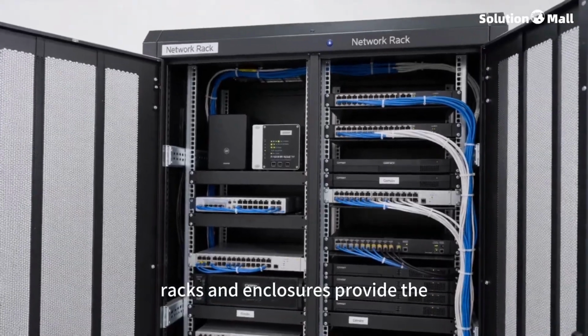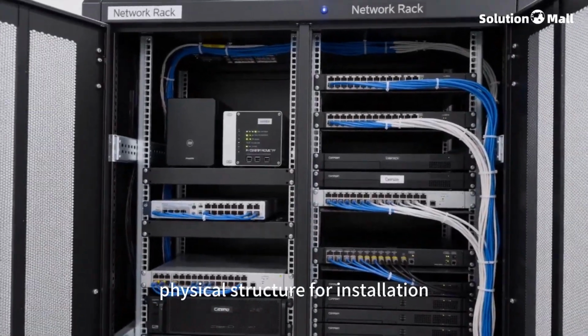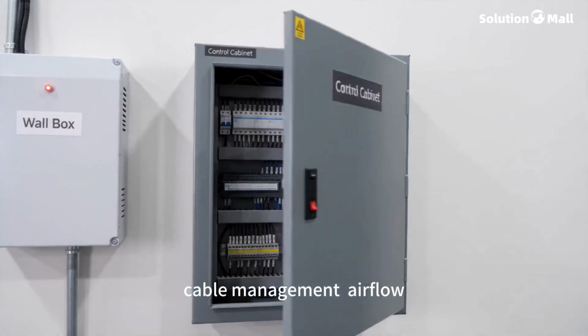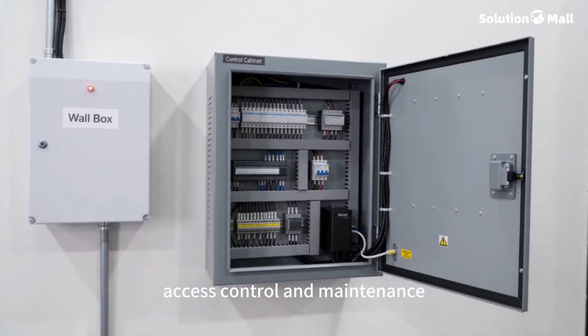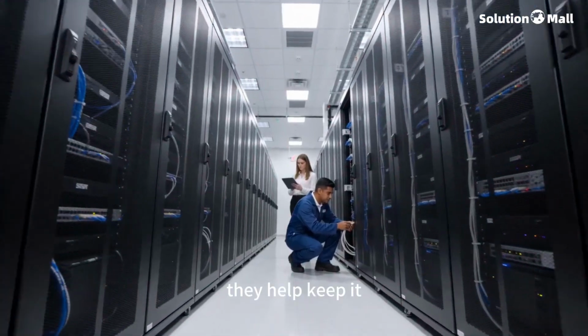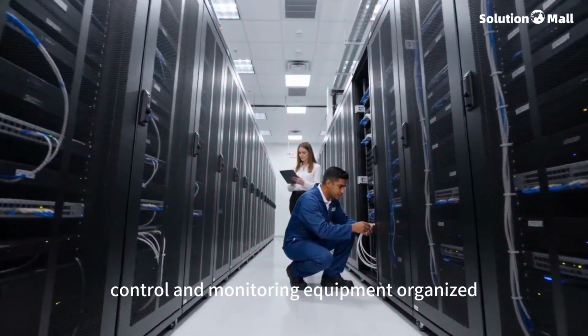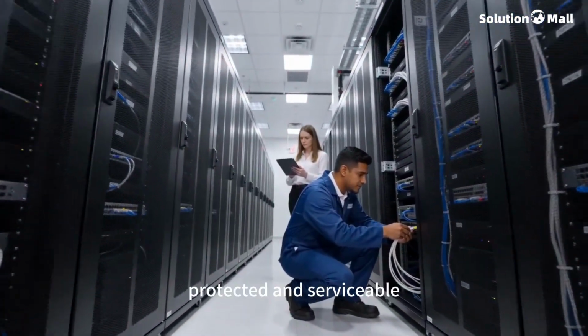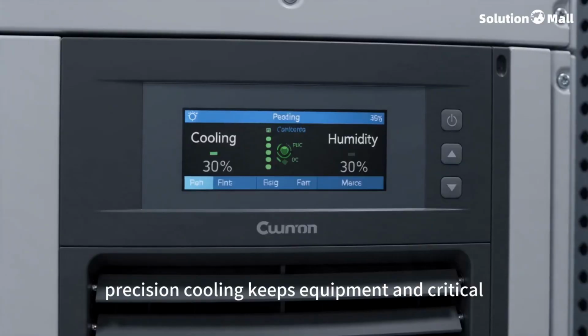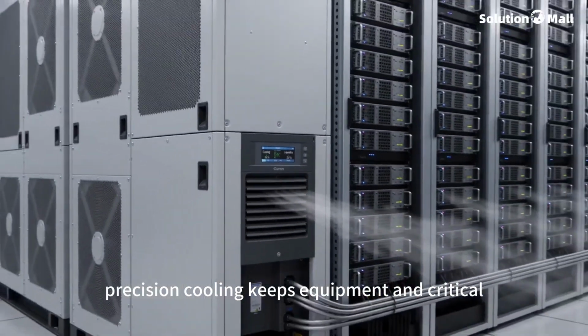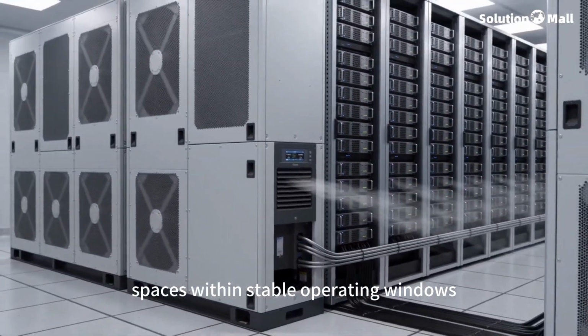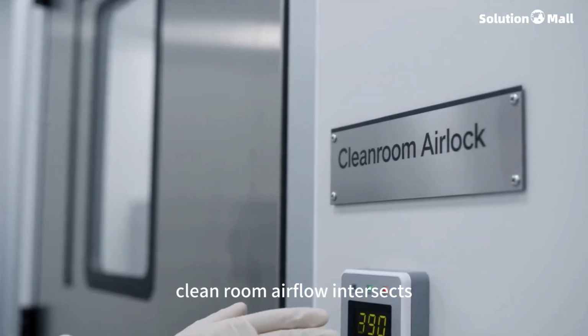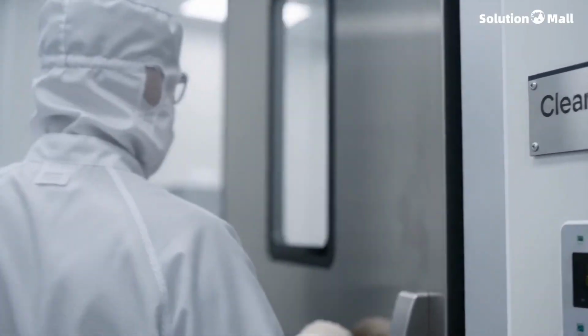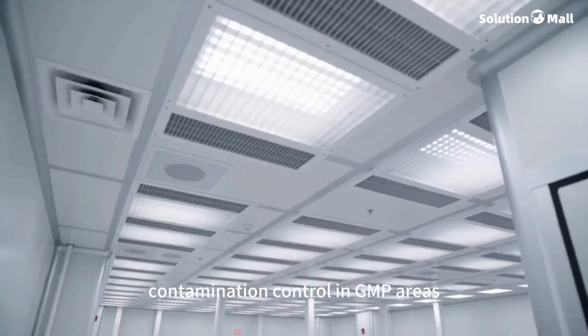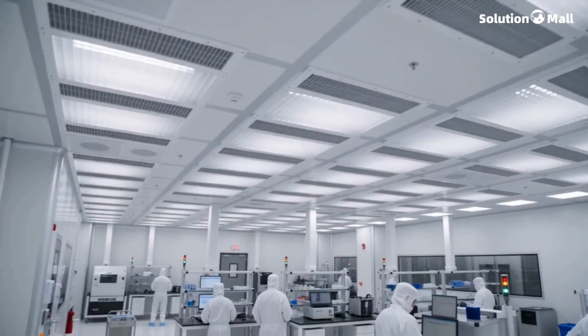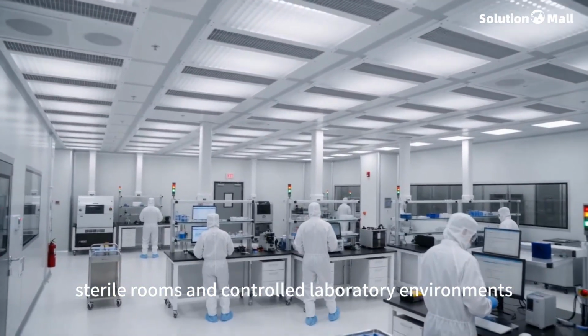Racks and enclosures provide the physical structure for installation, cable management, airflow, access control, and maintenance. They help keep IT, control, and monitoring equipment organized, protected, and serviceable. Precision cooling keeps equipment and critical spaces within stable operating windows. Cleanroom airflow systems support cleanliness levels, pressure stability, and contamination control in GMP areas, sterile rooms, and controlled laboratory environments.